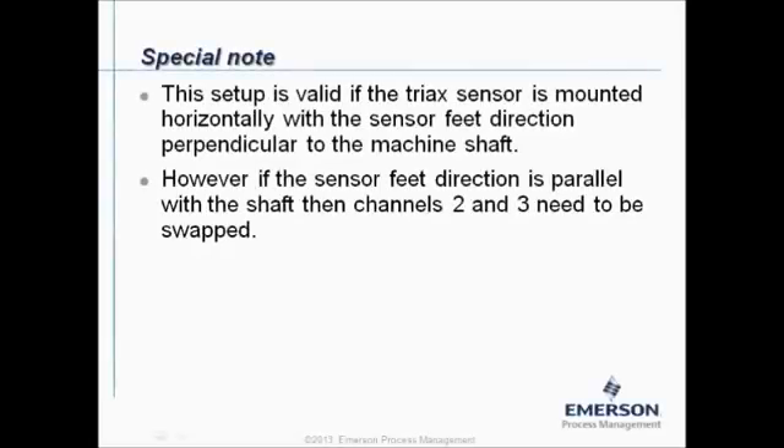Special note: this setup is valid if the triax sensor is mounted horizontally with the sensor feet direction perpendicular to the machine shaft. However, if the sensor feet direction is parallel with the shaft, then channel two and three need to be swapped.